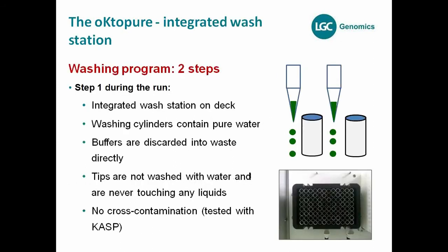The second big benefit of oKtopure is not just the throughput — it's also the cost for consumables. We've developed a washing program to avoid cross-contamination between the vials. Generally, this washing program contains two steps. The first step occurs during the run, using the integrated wash station on the deck.